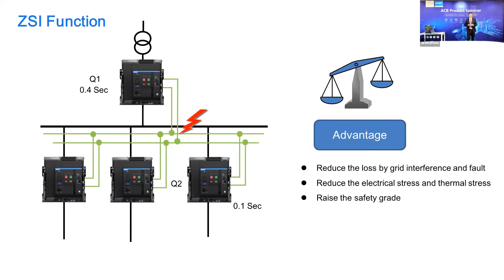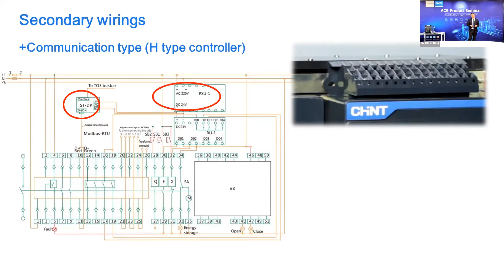Also for the secondary wiring: terminals 28, 29 for closing, 30, 31. These are the terminal numbers. You can see the second control terminal on the right top side. This is our terminal. If we use the H type, this is the communication type. We will put the ST-DP, the communication port, or even a power relay, and this is a control relay. If you use Modbus, because for other breakers we use Modbus, the standard port is RS485, and the port numbers are 10 and 11.